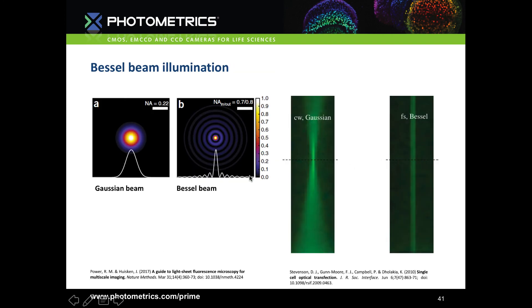Bessel beam illumination is another type of lightsheet involving changing the properties of the beam itself. A Gaussian beam is the standard, with its brightest point in the middle but a wide profile. The Bessel beam in contrast has a much thinner profile that propagates much further, giving effectively a longer lightsheet — but it comes with lobes that illuminate out-of-focus regions, compromising optical sectioning quality, degrading contrast and introducing photodamage. It's a trade-off to get a thin lightsheet with a larger field of view.